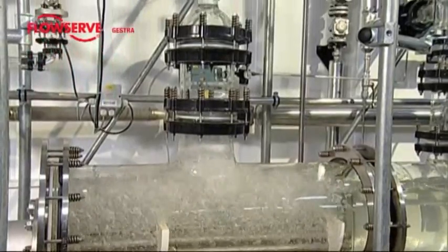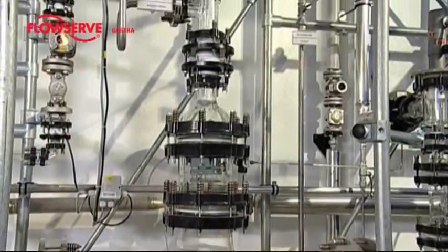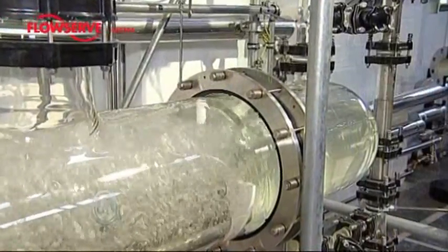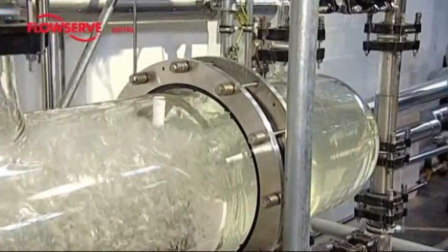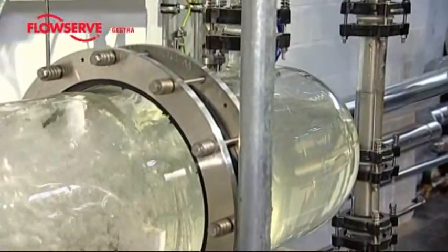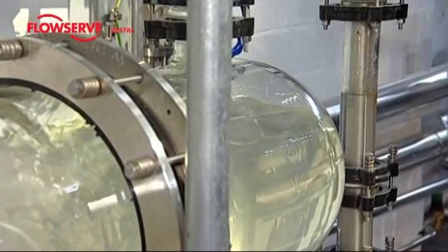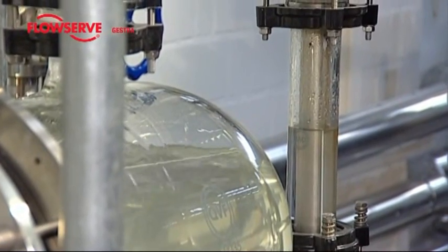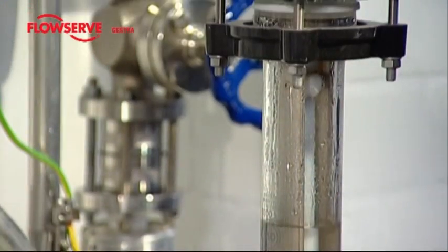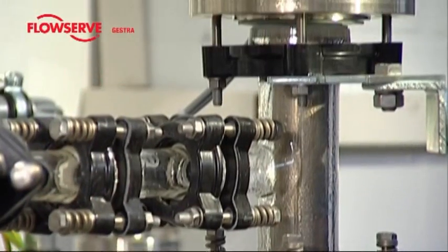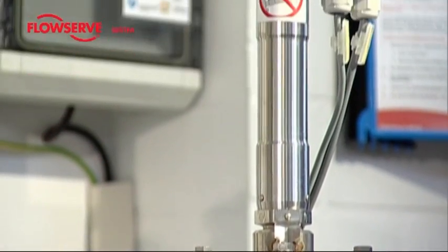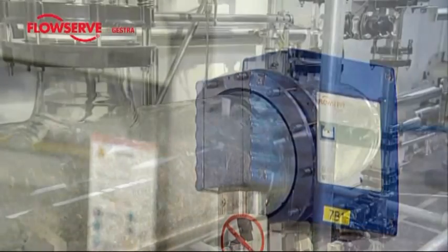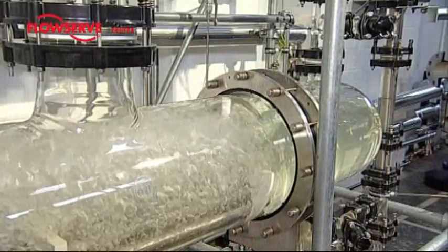This may lead to poor heating performance since the steam traps at the heat exchanger are not dimensioned for such quantities of condensate. Here it becomes clear just how important exact level measurement with only a very small control deviation is for steam boilers. An external measuring pot provides optimum measurement results. No matter how turbulent the surface in the steam boiler, the water level in the measuring pot will remain calm. Measurement takes place by means of a capacitive sensing system, delivering a stepless 4 to 20 mA signal. In this way, the water level in the steam boiler can be controlled with a deviation of only 1 to 2%. Such precise regulation is not possible if conductive level probes operating according to the on-off control principle are used.